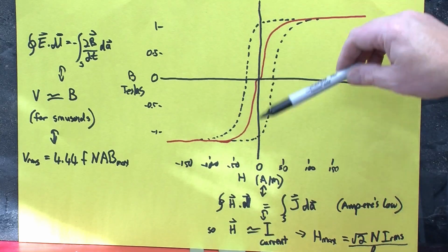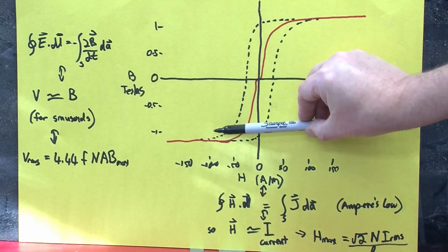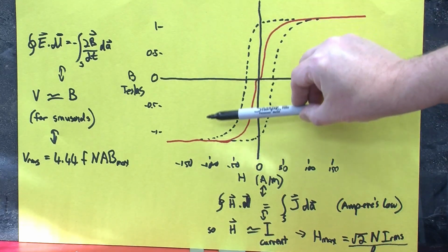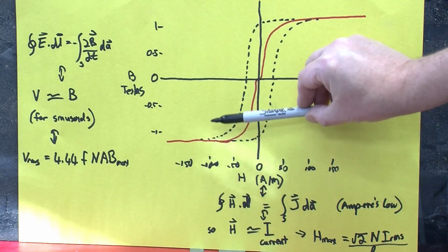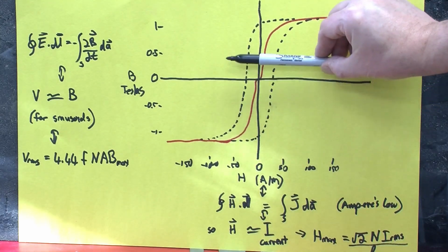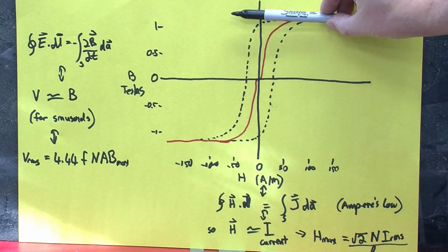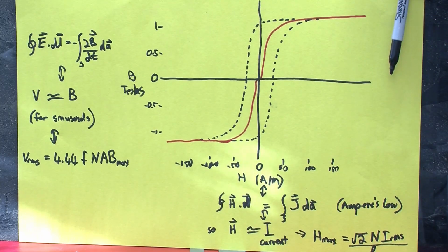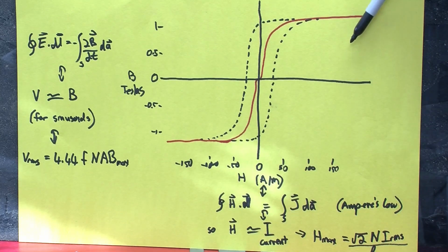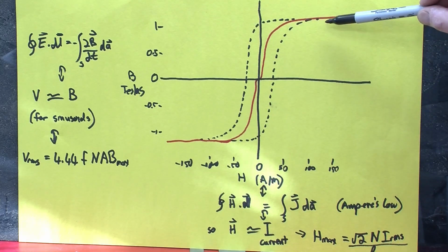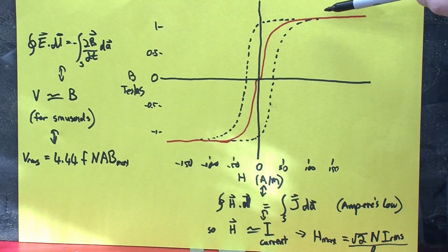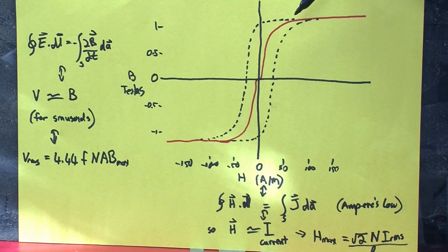Now look what happens when our voltage gets so high that we need swings in the B field that go all the way to the top of this graph. They hit the saturation point, and suddenly to keep going up we need huge amounts of current, and those huge amounts of current are the spikes we were seeing. That's the basic cause of those spikes, and it's also what essentially limits how much voltage you can put on a transformer, assuming the insulation doesn't break down.